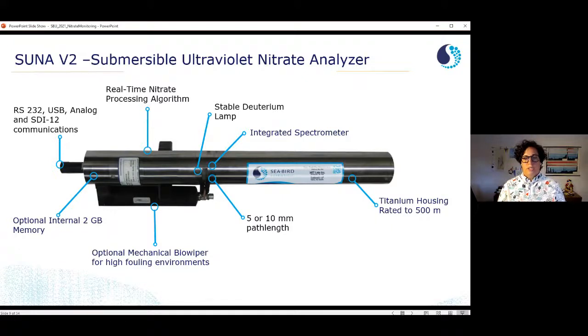Also part of it is the lamp. This is a spectrophotometer, so you need light. There's a lamp in there, and then an integrated spectrophotometer. Between them, there's a 5 or 10 millimeter path length. That depends on how much fouling you have, if you're going to have a lot of suspended sediment, and that's how to make that choice for your application as well. You can also get this with a titanium housing that's rated to 500 meters.